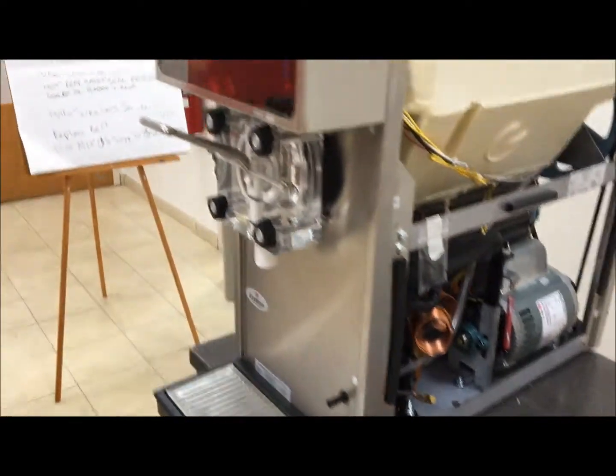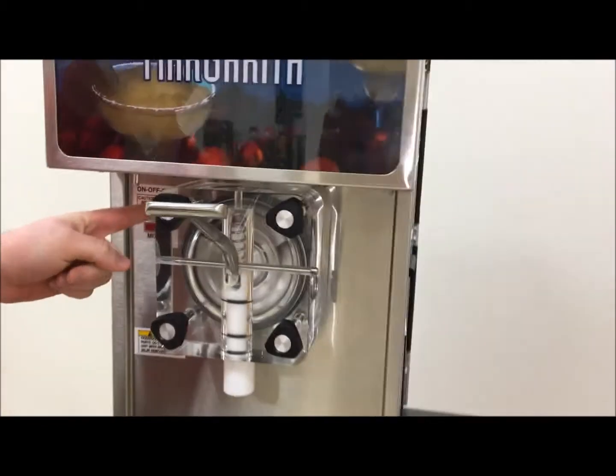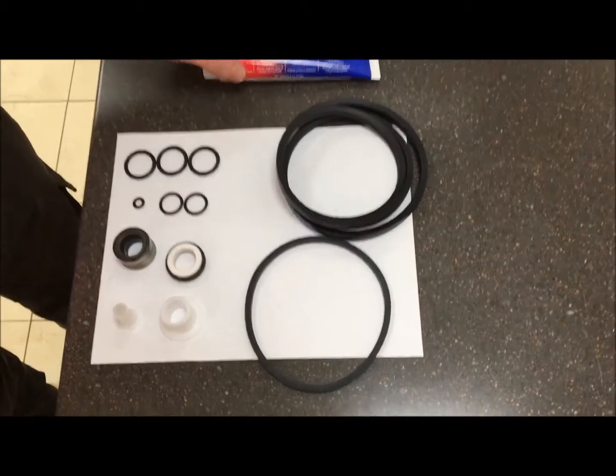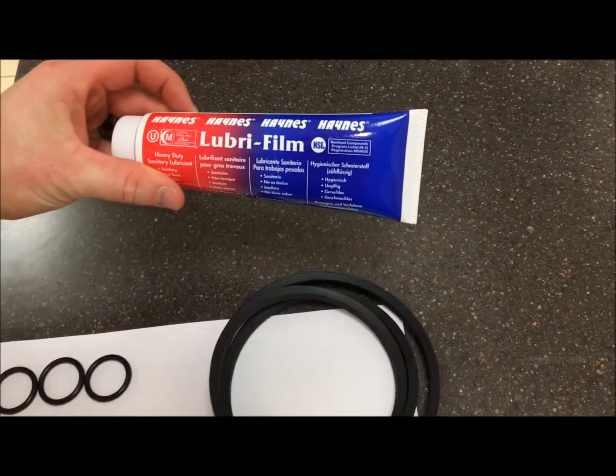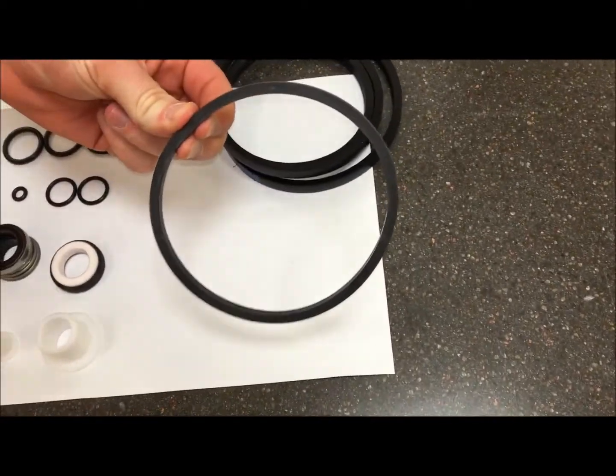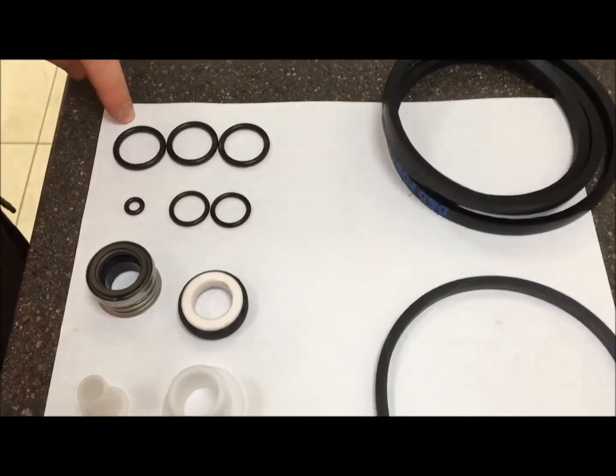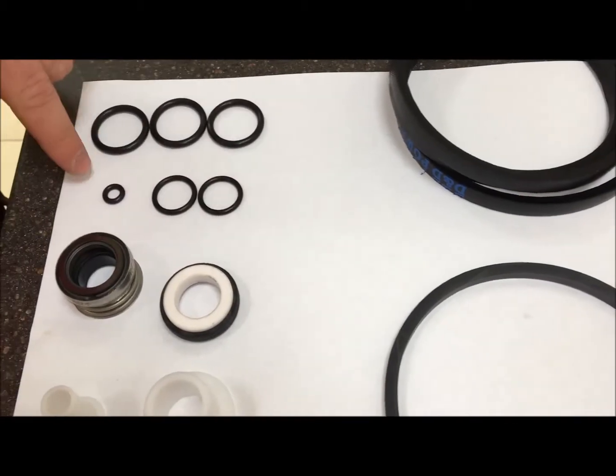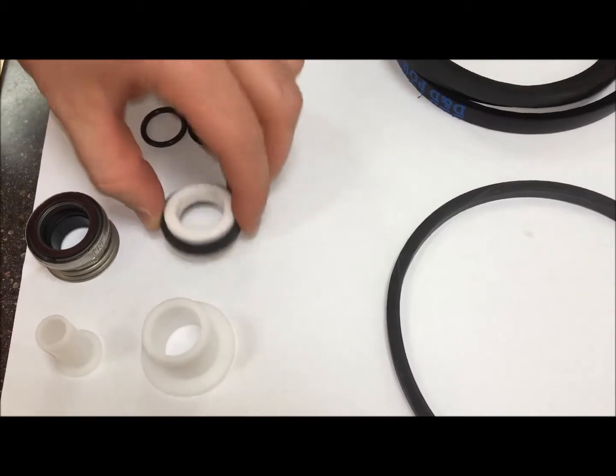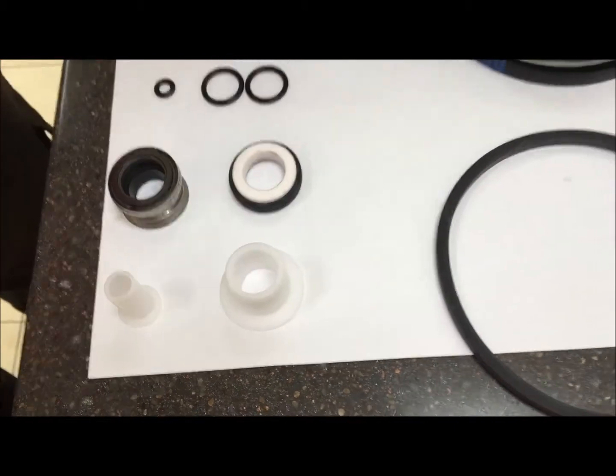You're also going to want to make sure that the machine is put into clean mode by having the switch turned all the way to the right, signaling clean. Inside your PM kit, or preventative maintenance kit, you should receive a tube of Haynes Lubri-Film, a belt, valve body O-ring, dispense tube O-rings, two carb tube O-rings, a float O-ring, a shaft seal set, a front Seder bearing, and a rear Seder bearing.